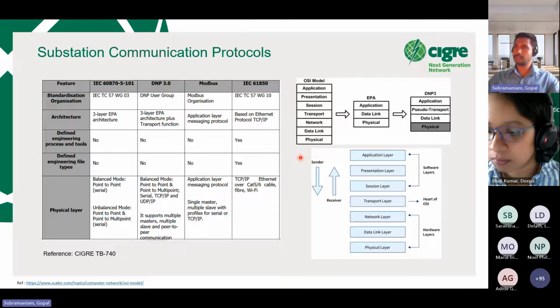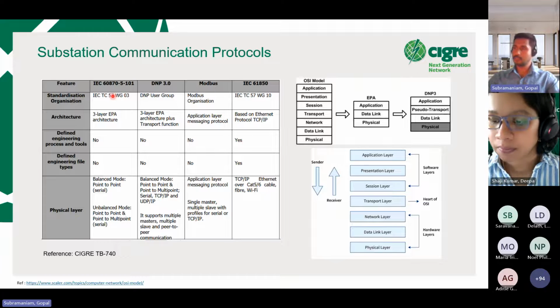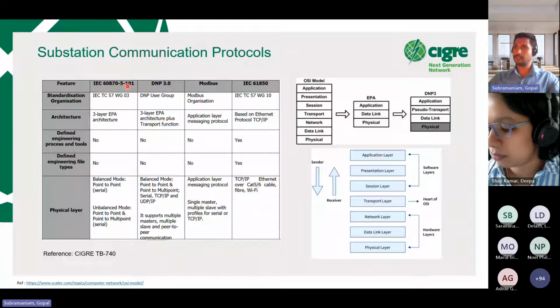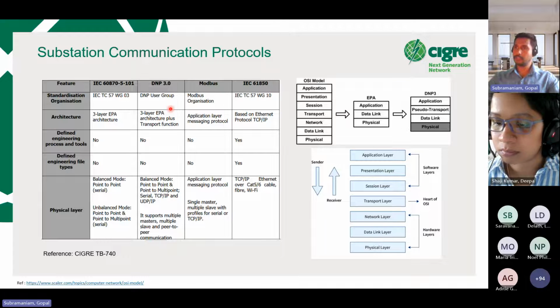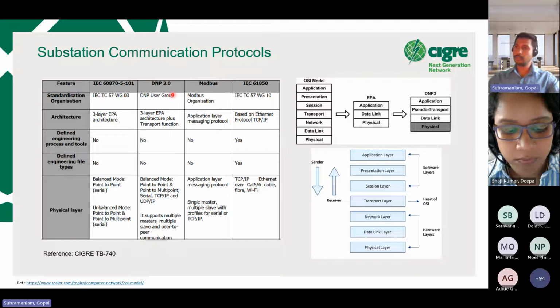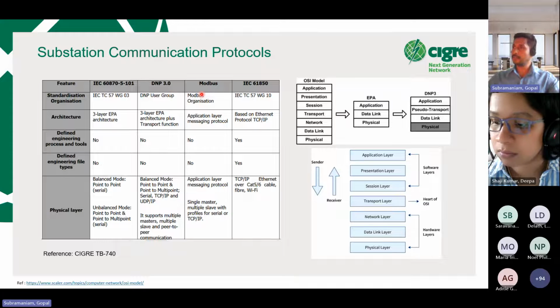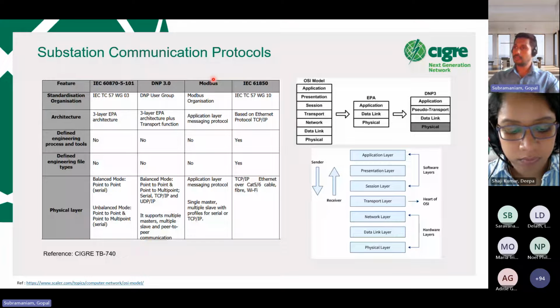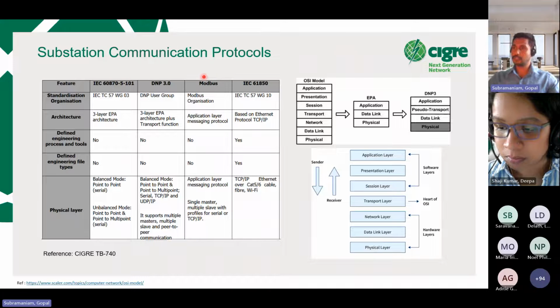And getting into the comparison of substation communication protocols, these are the most widely used communication protocols that you might have come across. We generally call it 101, like 60870-5-101. This protocol was developed by IEC. DNP3 was developed as a proprietary protocol by General Electric. Later, it was adopted into an IEEE standard, and this protocol is widely used in North America and countries like Australia. And Modbus, this protocol is almost being ruled out now. It is quite commonly used in the industrial automation area nowadays, but not in substation automation.